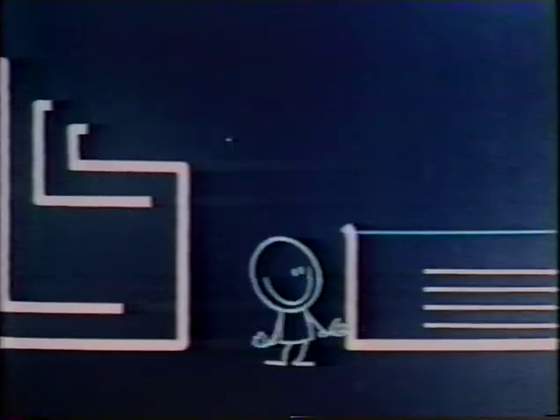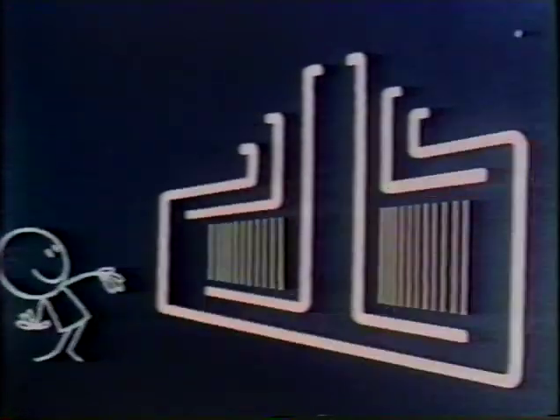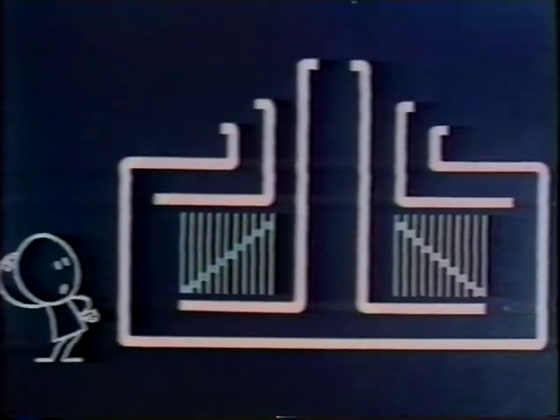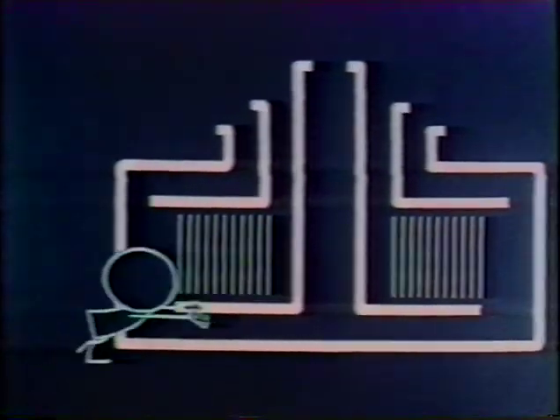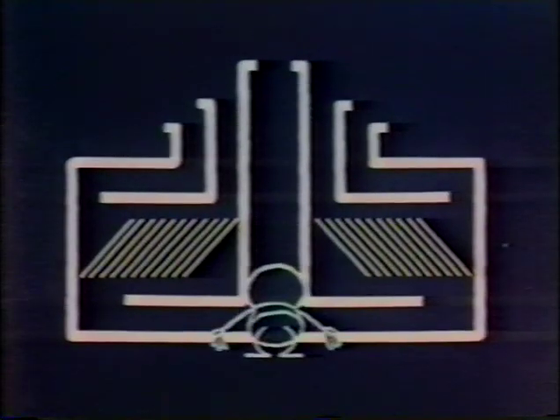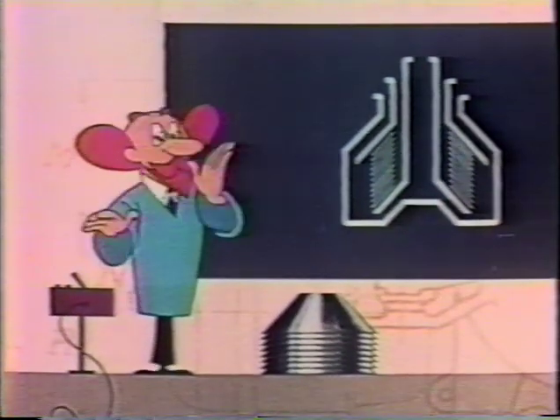Now what happens when we increased the rate of the feed? It meant there was not enough time for separation to take place. But let's take another look at our thin strata principle — we take a number of discs and put them in the bowl. But this answer is still not quite good enough, because the particles passing along the channels close to the centre are only subjected to a small centrifugal force. The channels around the periphery are much more efficient. Obviously we should try to make all the channels equally effective. Well, here's one thing: we can turn the cylindrical trays into conical discs, and then alter the shape of the bowl to conform with the shape of these discs. A simple little idea, but important.